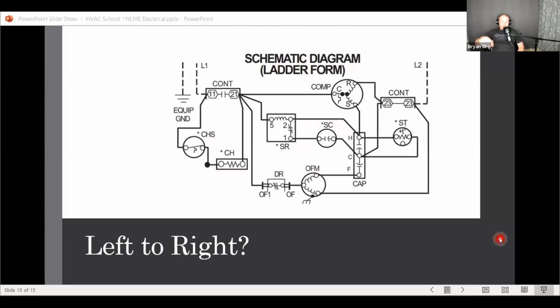I take them off at the compressor, I tape them up, and then I put everything back together and start it back up. And if everything else runs, and before it was shorted out and tripping a breaker, well, now I've isolated the problem down to the compressor. This is the number one way that good diagnosticians diagnose: they do isolation and confirmation versus just using a meter saying, hey, it's bad, and then moving on. You always have to confirm at the actual device, isolate. And if possible, use other parts to replace to even check and make sure, to double check.